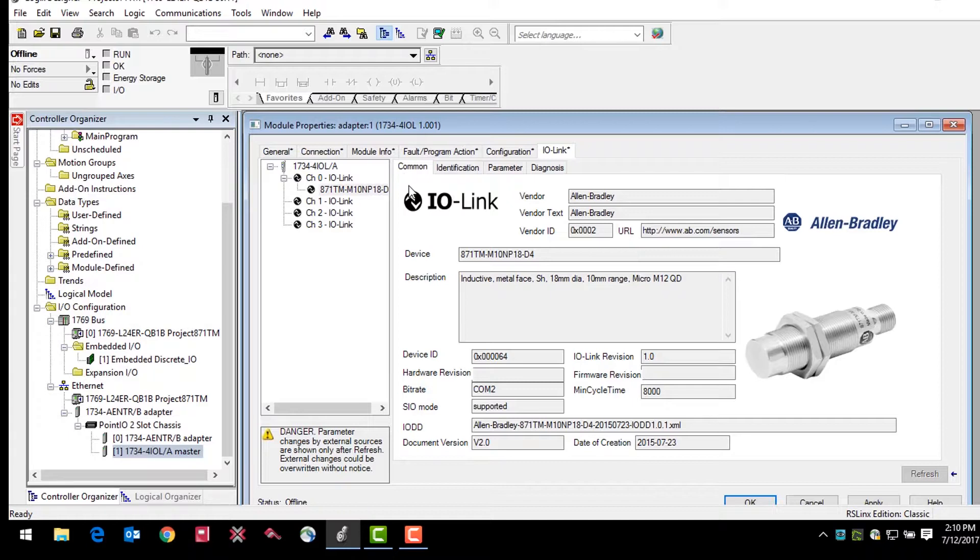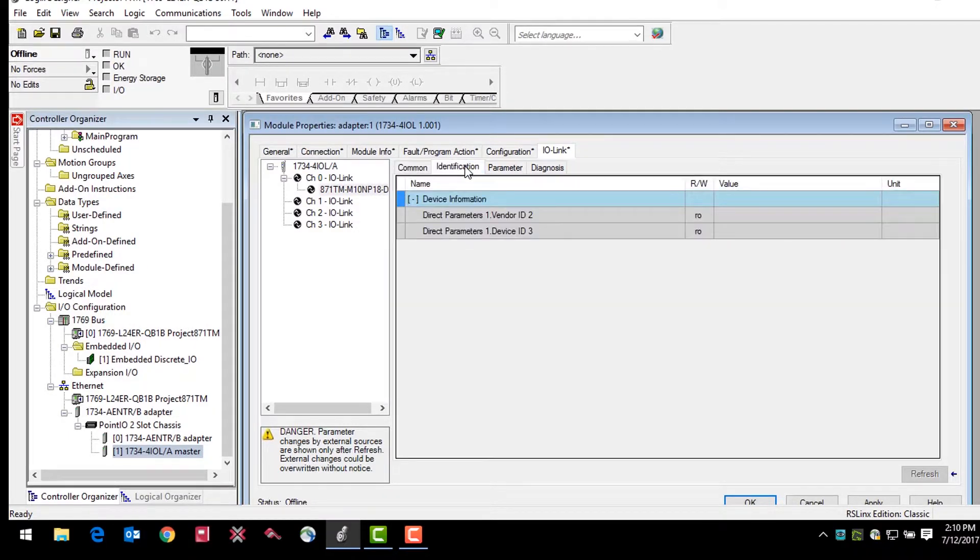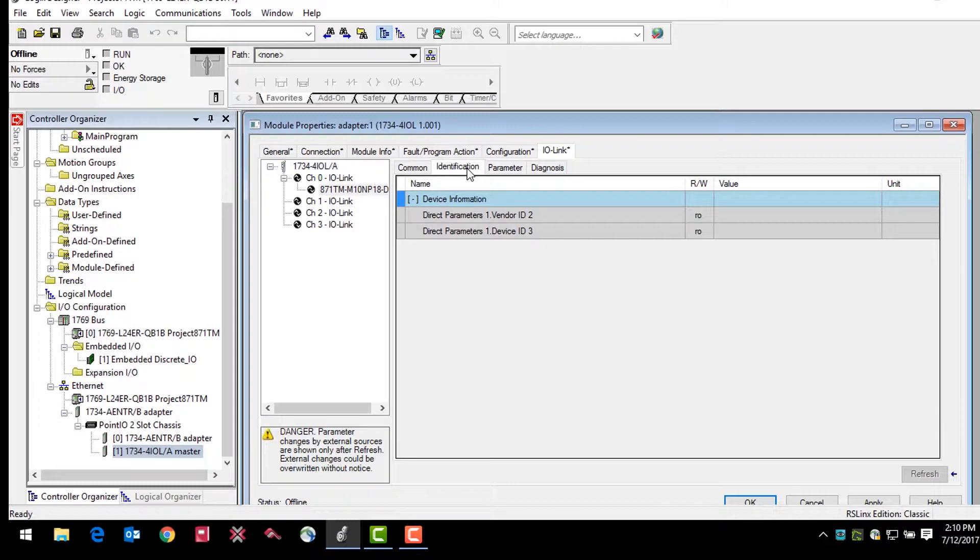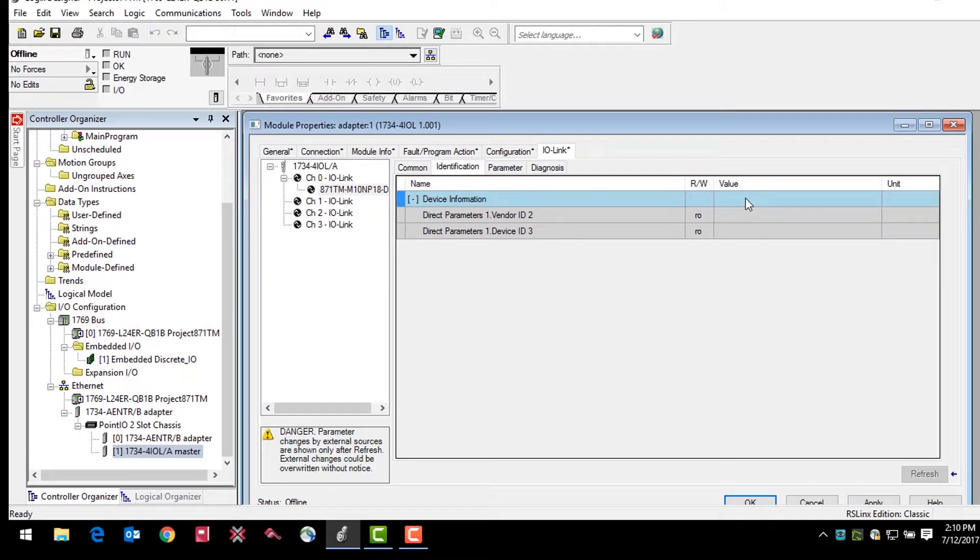The identification tab shows device information, such as specific vendor ID and device ID for the exact sensor that is configured. These fields are automatically populated per the sensor information. These fields are read-only as is identified with the RO on the screen. If we were online with the sensor, there would be values appearing in these tabs because the parameter values are read from the connected IO-Link device.